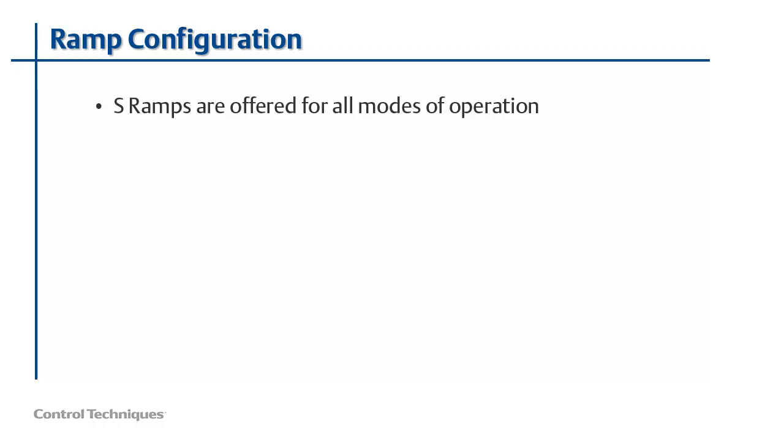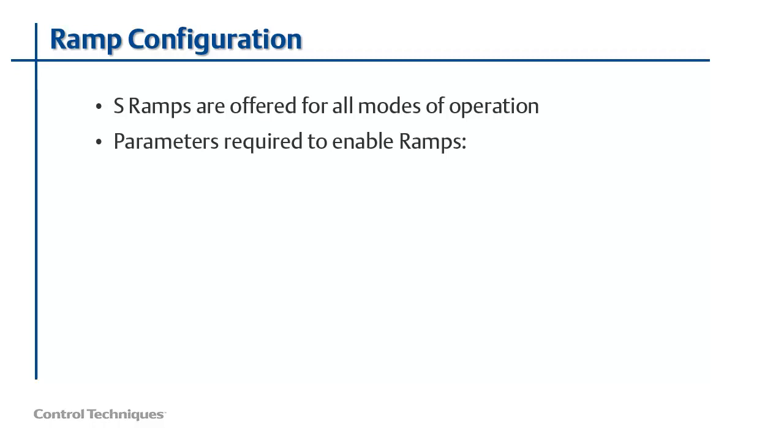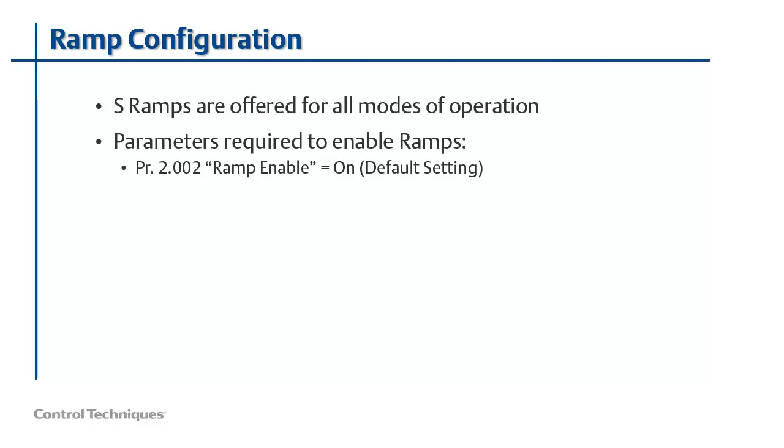To begin using the ramp system, you've got to ensure that ramps are enabled. Most of the ramp parameters are located in menu 2. The parameters that will enable the ramp system are parameter 2.002, which is ramp enable, and that is on by default. And then the drive stopping mode, which is located in menu 6. Parameter 6.001 is set to coast by default. In that mode, the drive will use your acceleration ramp to accelerate the motor, but when a stop is active or the run signal is removed, the drive will coast to a stop and ignore your programmed deceleration ramp.